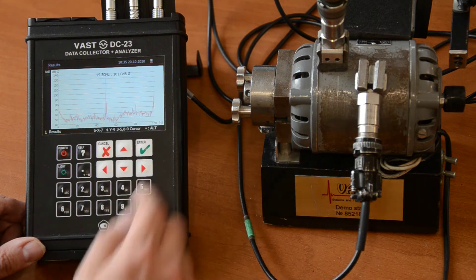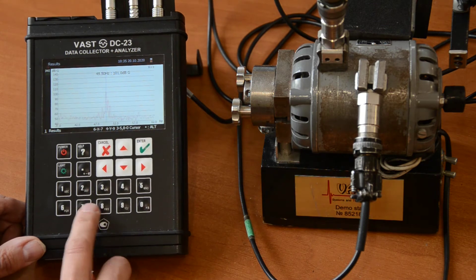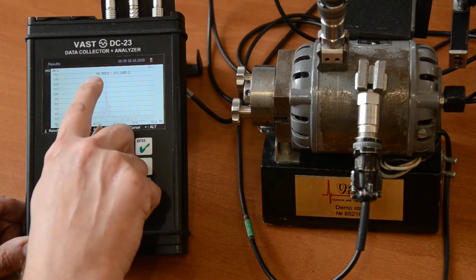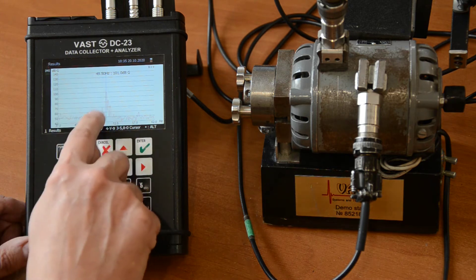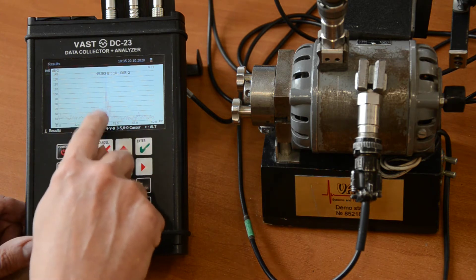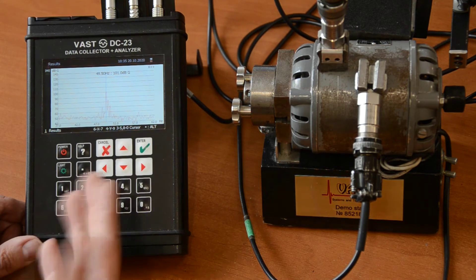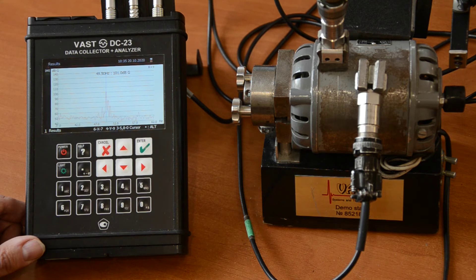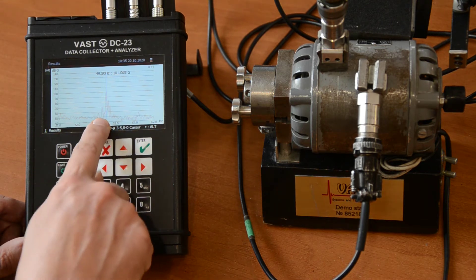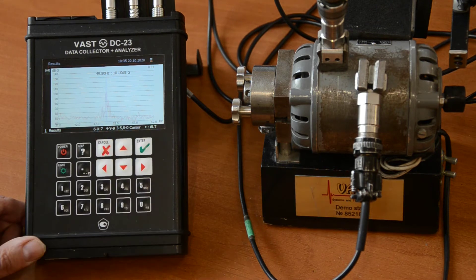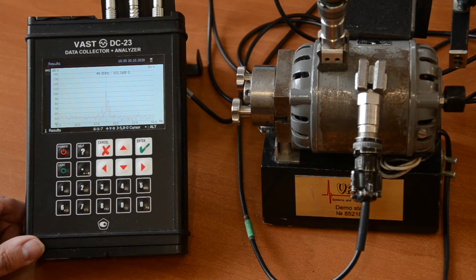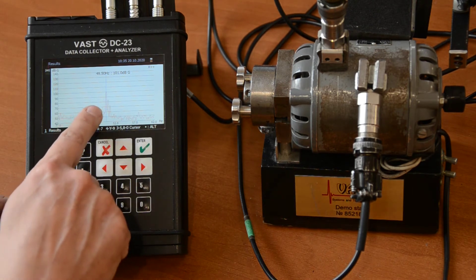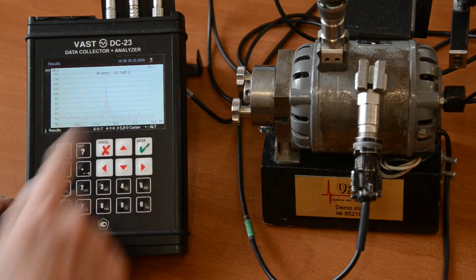If I go to here and zoom it, I see that my rotation speed, that is 49.5, it's split into many lines. I have many sidebands. This is the sidebands on the slip frequency. And in this way, I can make diagnostics of the squirrel cage. So, this is a defect of the squirrel cage. If it was a single line here, I would say that the motor is in good condition. But in my demo stand, I have damaged squirrel cage. And because of this, I have very many sidebands.